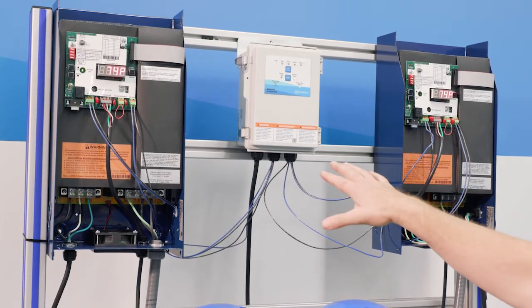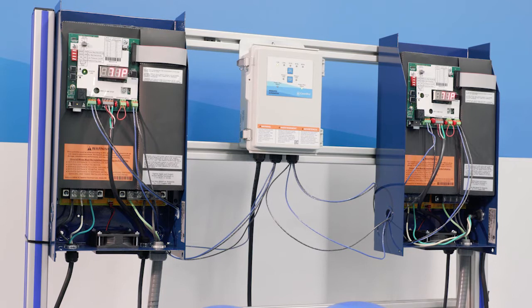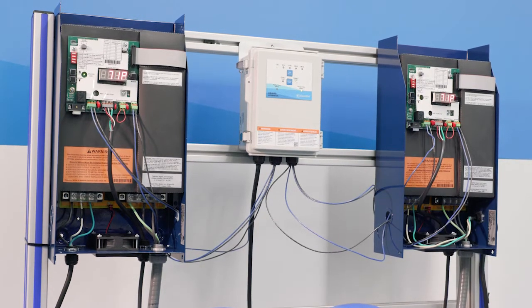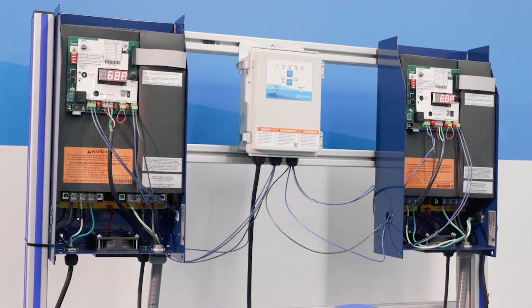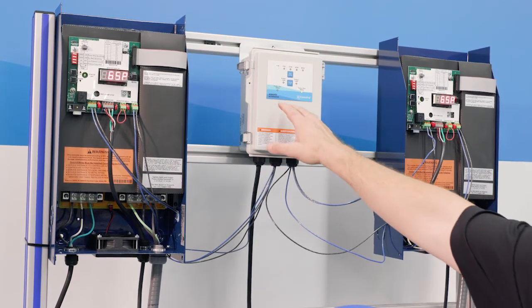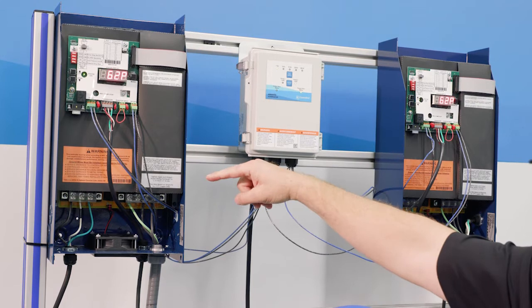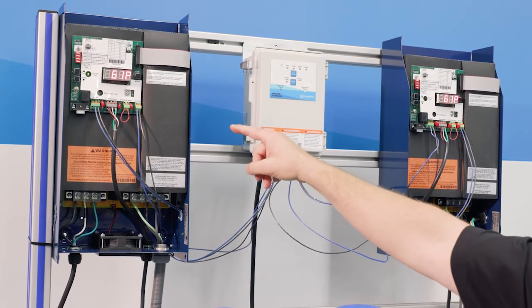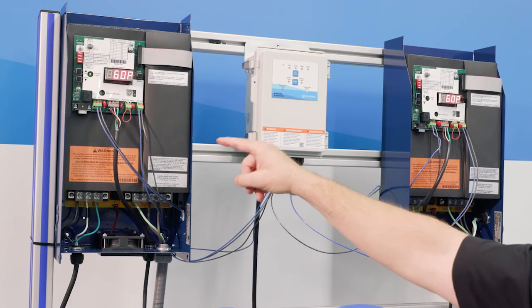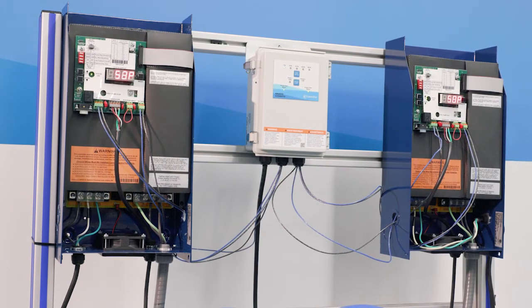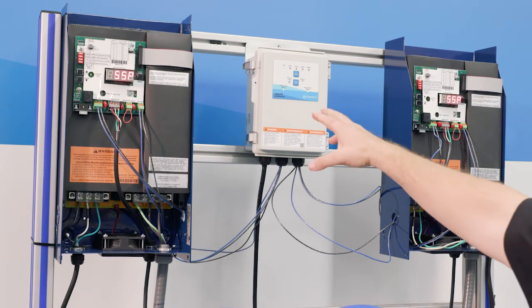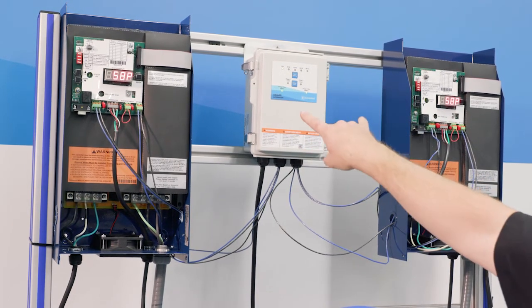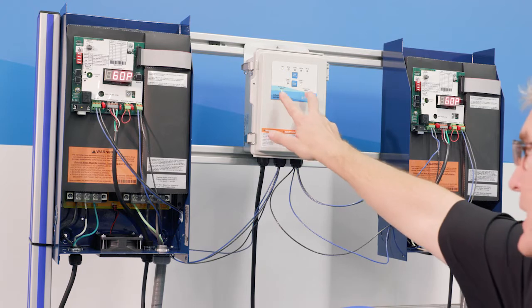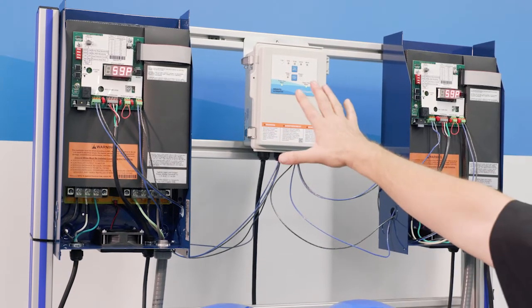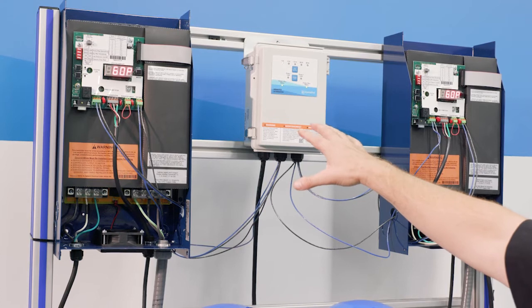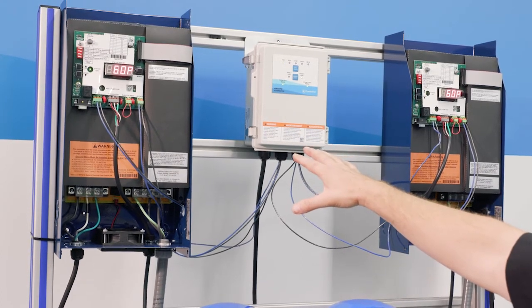All right, so let's give it some more demand. Pressure's dropping. Now what we're going to see as I open this up is pump 1 come on when it gets 5 psi below the lag pressure, which was 60. All right? So now we've reached that point. Now we've got both pumps running. You can see here, both pumps are running, and they're maintaining the lag pressure, which in this case was 60 psi.